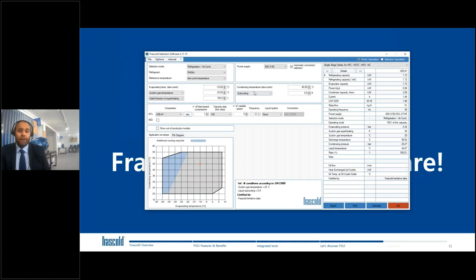Box of discharge condition, so the condition in the condenser. You can set the condensing temperature, dew point, and the subcooling. If you have the information not of the subcooling but directly of the liquid temperature, you can set the liquid temperature directly. I put 1 just to have an idea.